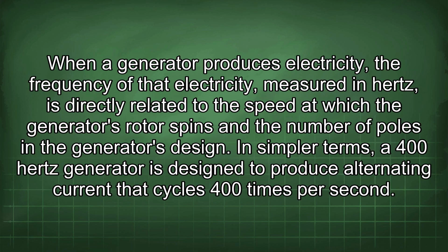When a generator produces electricity, the frequency of that electricity, measured in Hertz, is directly related to the speed at which the generator's rotor spins and the number of poles in the generator's design. In simpler terms, a 400 Hz generator is designed to produce alternating current that cycles 400 times per second.